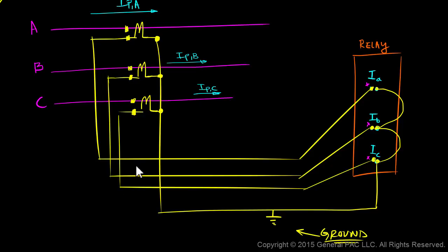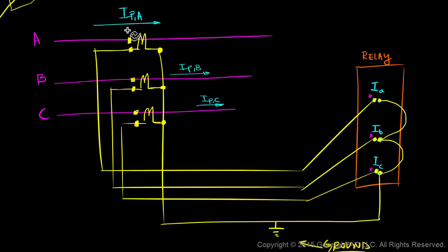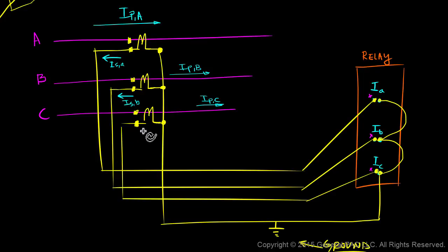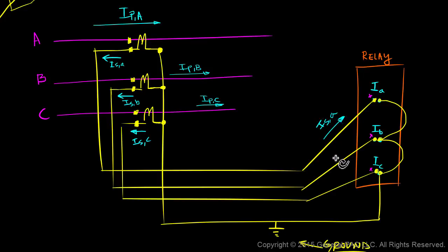In this module, let's focus on these currents. Since the primary phase A current flows into the dot on our primary side, the secondary phase A current must flow out of the dot on the secondary side. Similarly, secondary phase B current and secondary phase C current must also flow out of the dot on the secondary side. Secondary phase A current flows into the polarity-marked input terminal in our relay — same thing with phase B and phase C current. What comes out of the non-polarity side from our phase A input terminal is essentially phase A current.